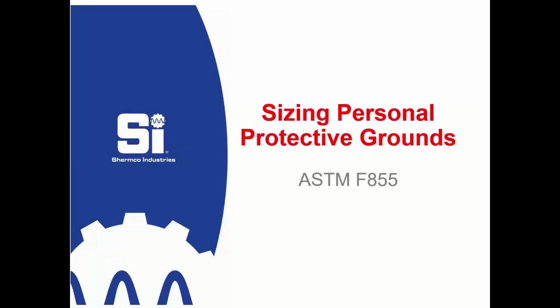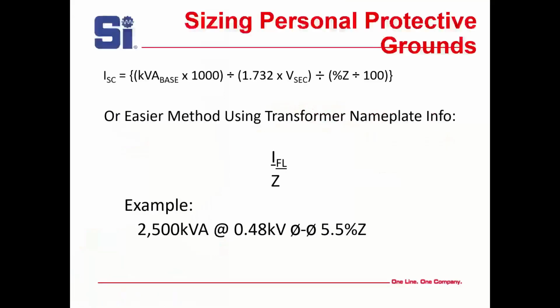So let's size personal protective grounds according to ASTM 855. Now, this is not from 855. This is your base calculation. The short circuit current, which you have to know, is the base kVA of the transformer times 1,000 divided by the square root of 3 times the secondary voltage. That's not seconds, that's secondary. And then you divide that by the percent impedance divided by 100. I don't like long calculations. Most of this information you get off the data plate. As long as you know the full load current, that can be calculated easily. The impedance percent comes off the data plate.